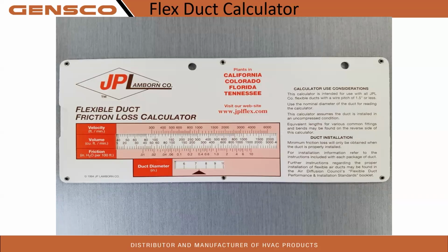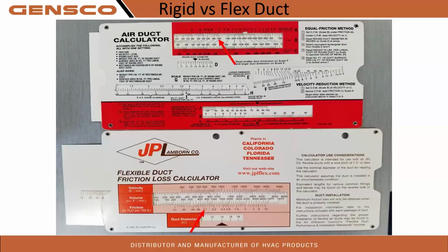Flexible duct. Again, this is a different calculator for the flexible duct. I'm going to show you the difference. Look at this, rigid. Here's rigid, right? So this is a 14-inch round, or 10 by 17, or 8 by 22, right? At 0.1, we're 1,000 CFM on 14. And at 0.08, we're about 900 CFM. So let's just go off of 0.1 for this example. We're 1,000 CFM. So 14-inch flex duct at 0.1, look at that. We're at like 750. That's a lot of airflow that we're not calculating for if we're using the wrong instruments to measure our airflow. So if we're having airflow issues, we'll be able to see something wrong with it if it has flex duct.